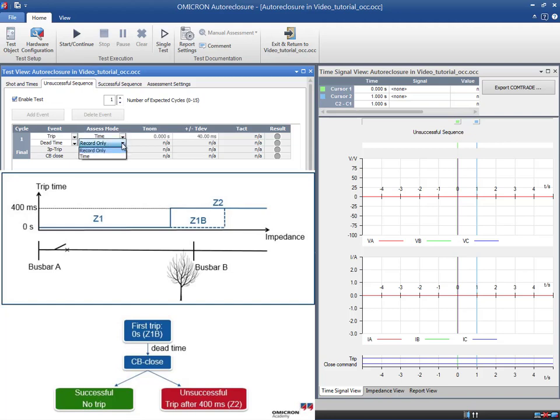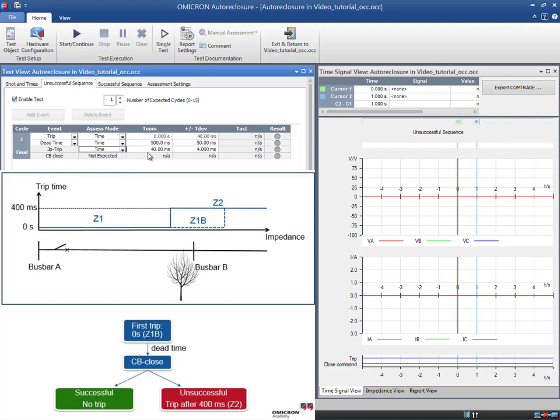The second event is the Dead Time, which is set to 500 milliseconds in our relay. An Unsuccessful Sequence implies that the fault is persistent, forcing the relay to trip again. In our relay, Zone 1B is deactivated after the auto-reclosing to ensure selectivity in the network. Consequently, a relay located at Bus Bar B is able to trip in the event of a fault beyond this location. For this reason, we expect our relay, which is located at Bus Bar A, to trip at the time of Zone 2, that is, 400 milliseconds. Because we are testing one auto-reclosure cycle, no CB close is expected after the second trip.